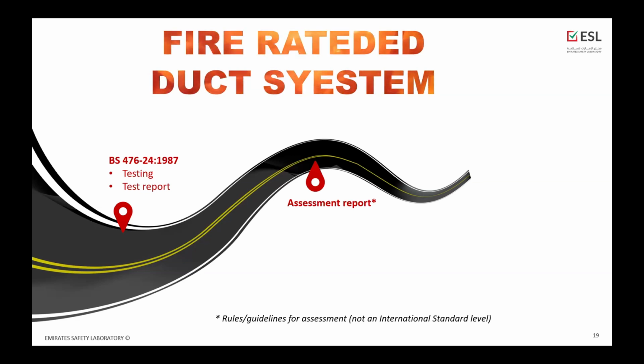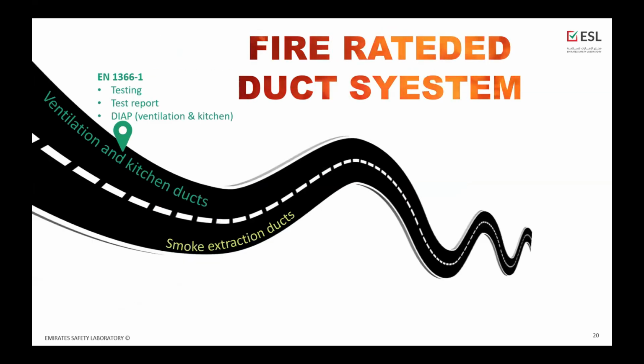It is good to highlight that during the assessment report we need to be very careful, because in most cases we test a duct with a width of 1 meter and a height of 250 millimeters. So giving an assessment for a size equal to, let's say, 10 meters by 10 meters is quite dangerous, so it must be done with all responsibility by the authorities preparing the assessment report. At the end of the road is also the certificate, which is issued by the certification body. For EN ducts, the EN approach looks a little different and has two lanes. The one lane is for ventilation and kitchen ducts, tested as per EN 1366-1.